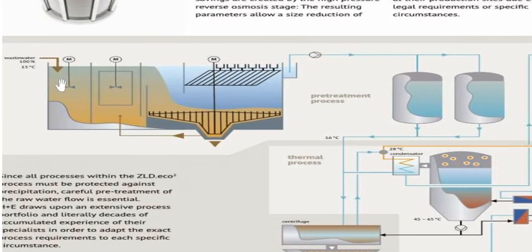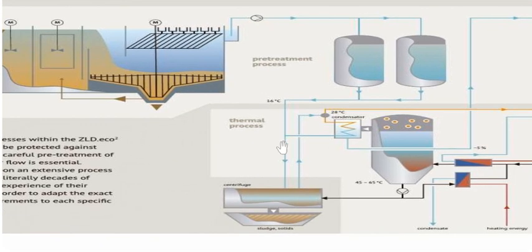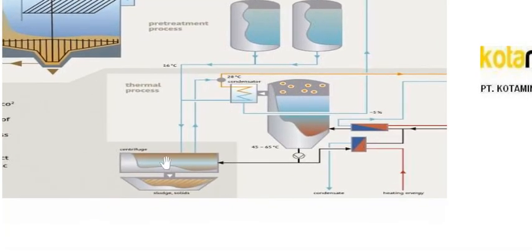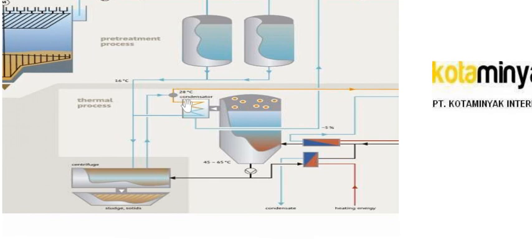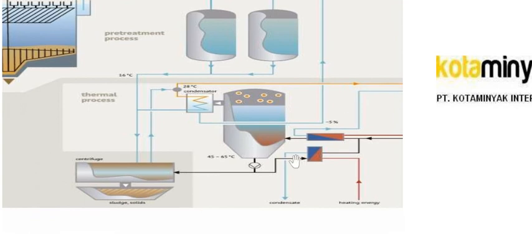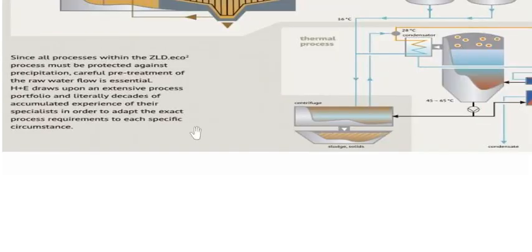So the wastewater comes in 100% at 15 degrees Celsius entering the ZLD system. So we do the pretreatment process and then the thermal process. Here we have centrifuges and sludge. Solids, this is the end point. This is a condenser, to make it cool, and then raise the temperature again to 65 degrees Celsius. The heating energy, the condensate is the cooling. That's how you do it.